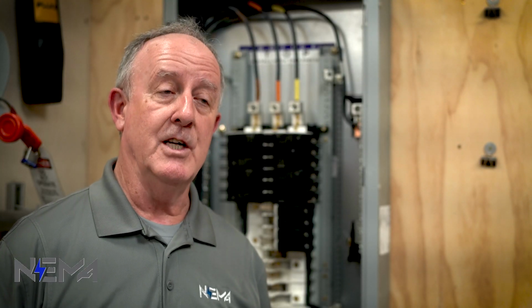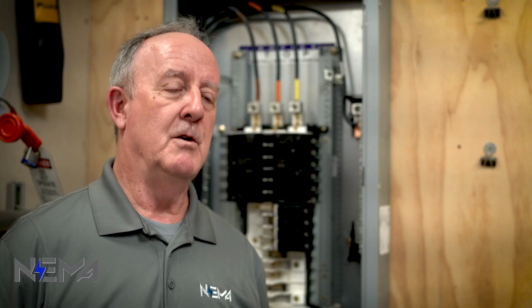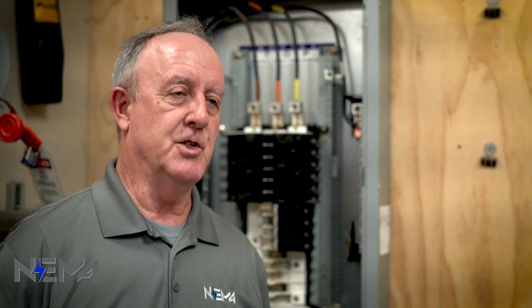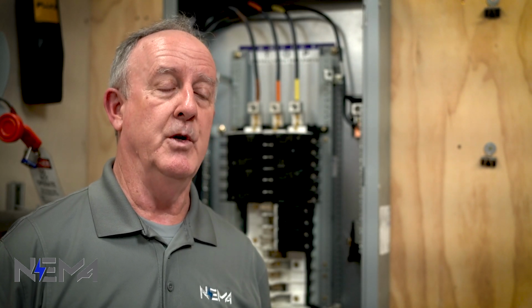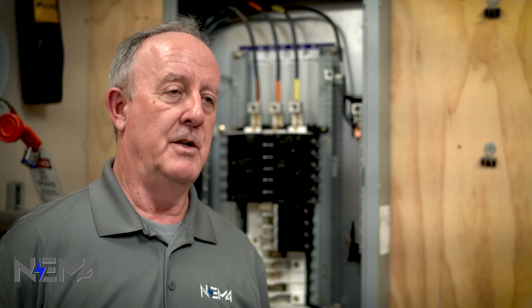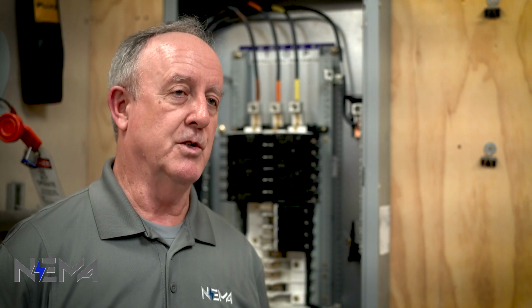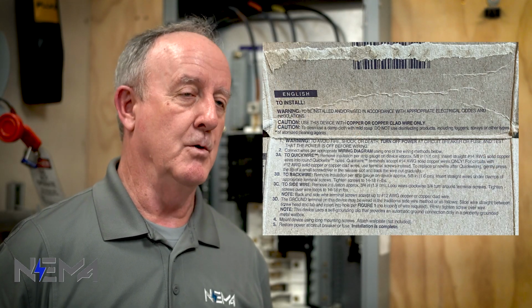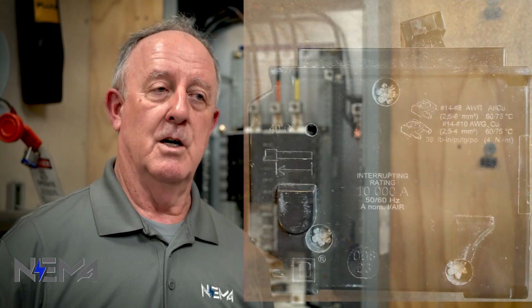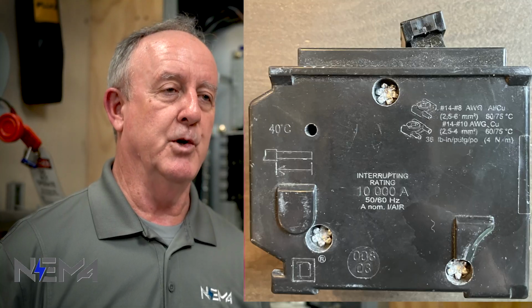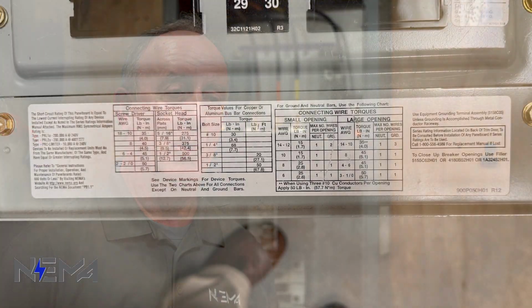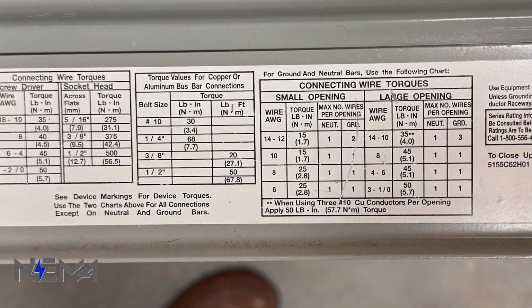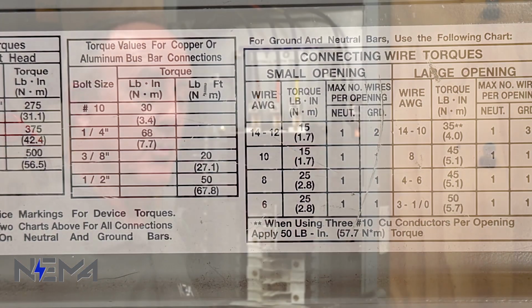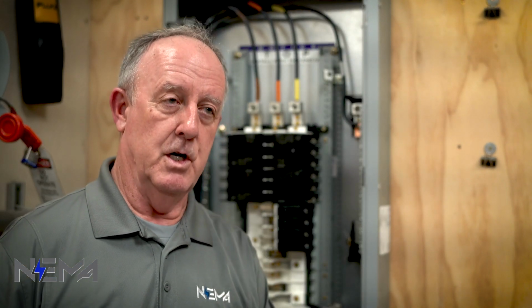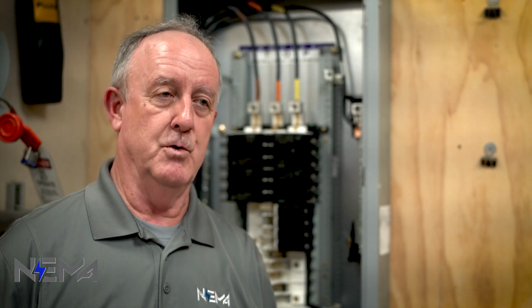And what types of connections need to be properly torqued? Virtually all. The manufacturers are going to indicate on their equipment what those torque values are. In the case of wiring devices, it can be marked on the box that the switch or wiring device comes in. On a circuit breaker, it could be marked on the circuit breaker itself. On panel boards or equipment like we're looking at today, it's marked on the cover. So you would look on the cover there and it'll give you the torque values for those terminations.